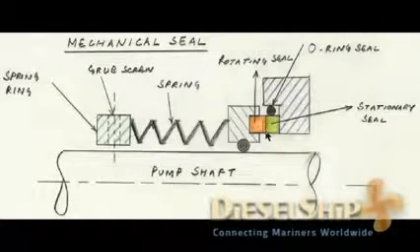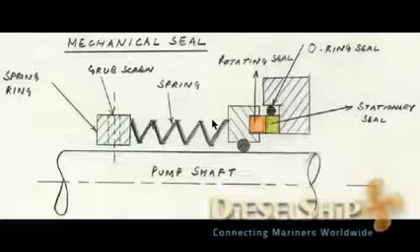And you have to remember one thing: there is definitely a fluid, or lubricating oil film, or process fluid film, between the primary seals. This acts for two purposes. One is to reduce the friction, and the other is to lubricate and remove the heat from the rotating and stationary parts. So that's it about the mechanical seal, and probably we will see the dismantling and mounting on a pump shaft, how exactly it is done and what the points to check for are.